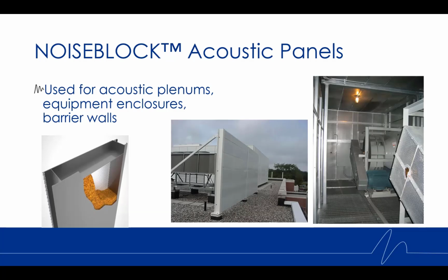So you can see an image in the middle here where we have a chiller on one side, and we've made a barrier out of these panels to block the noise and to mitigate the outdoor sound path. The panel is generally constructed with perforated sheet metal on one side. That's going to be the side that faces the equipment. There's fiberglass on the inside, so that's going to absorb a lot of the noise that's being emitted and prevent any sort of reflections from happening. And then we have a solid sheet metal on the outside. These have a painted finish and can look really nice once they're installed.